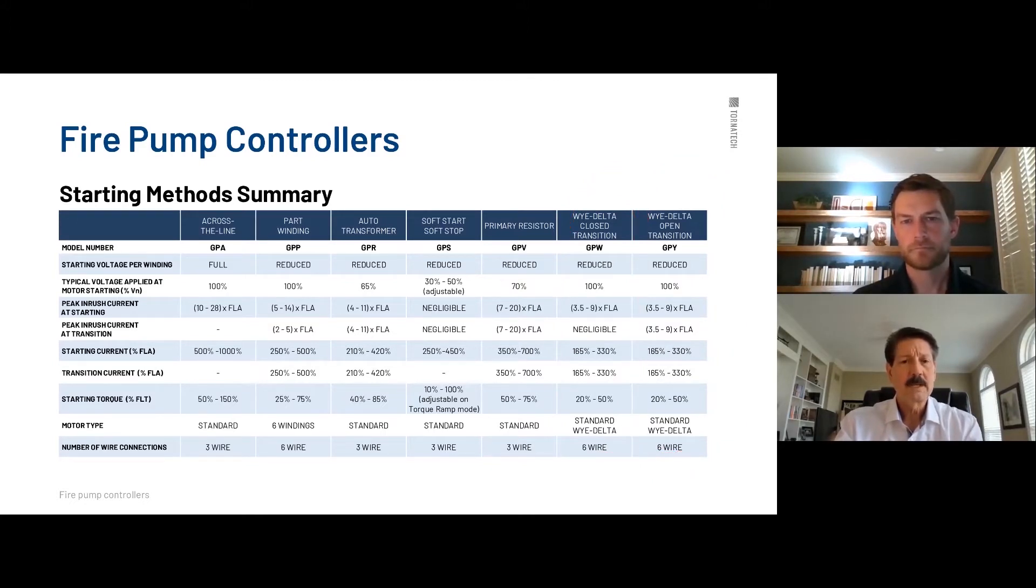The big thing here, as you'll note, three wire, three wire, three wire, six and six. Typically again, when you get into this type of a design, reduced voltage is always trying to reduce the current inrush in an electrical system. High inrush is an electrical system cause adverse effects to the electrical system. It could actually induce noise and spikes back through the system, which could affect other electronic equipment within talk about critical production areas, hospitals, radio stations. I mean, different things where you could have that noise impact on the electrical system itself.